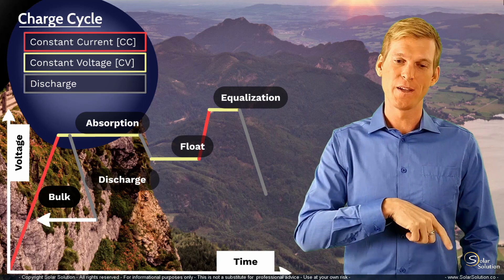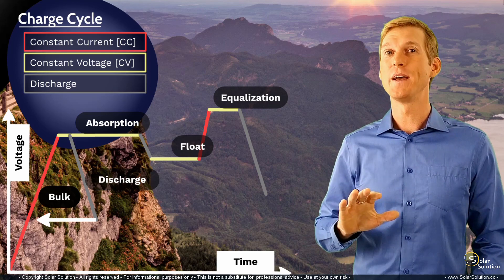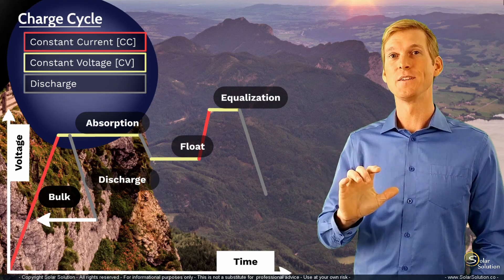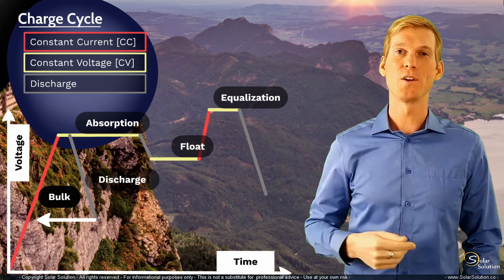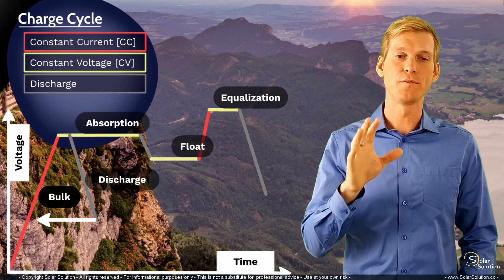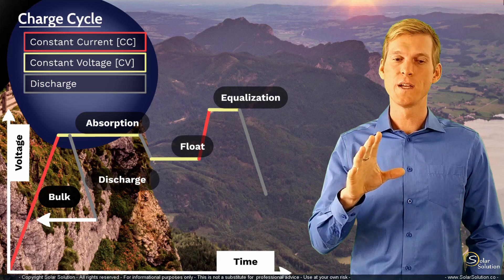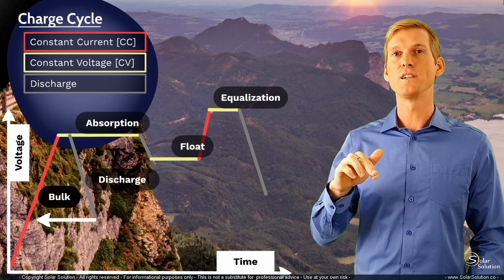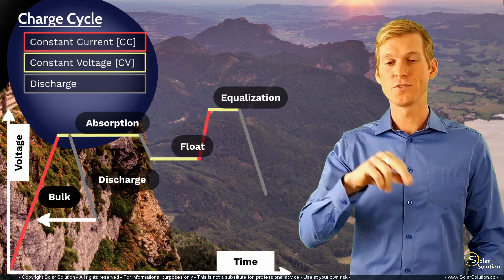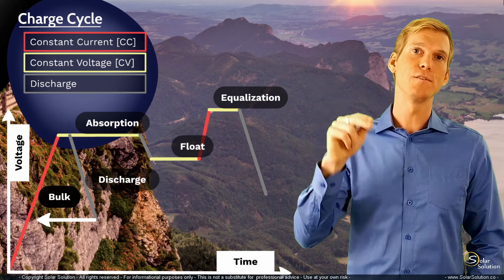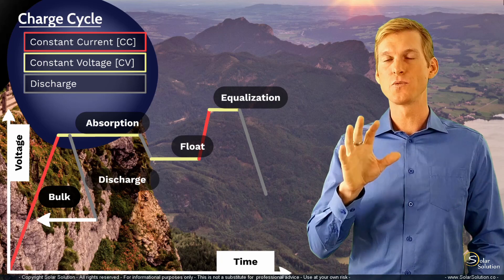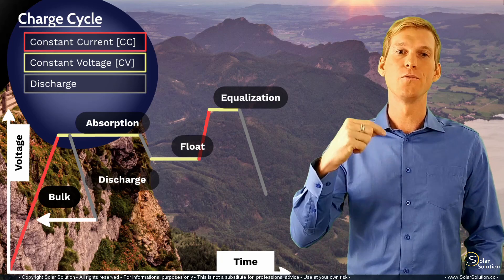So you start to push current into the battery at a constant current rate, until you've reached the absorption voltage again and the process starts all over again. But just remember that for many batteries it's quite important that at least on a regular interval you actually complete the whole cycle, so you run completely through the bulk and absorption stage until you have reached the float stage. So for certain batteries it's quite important that you do this on a regular interval.